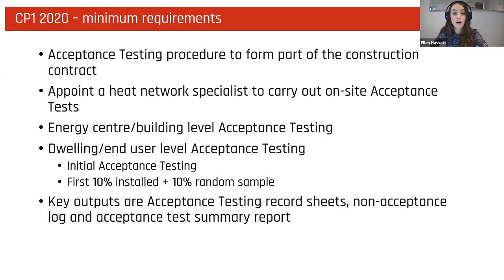So these acceptance tests are testing the energy center with a focus on average flow and return temperatures, efficiency, reliability, etc. And then acceptance testing of dwellings, which includes an initial set of tests on a small number of dwellings to establish systemic issues that can be rectified before commissioning and testing the rest of the development. And then taking a graduated risk-based approach to the rest of the development. So that's testing the first 10% of dwellings and then a randomized 10% sample of the remainder. And if any of those fail to meet requirements, then a further 10% should be tested, and so on. So the key outputs here are record sheets, a non-acceptance log, and a summary report.